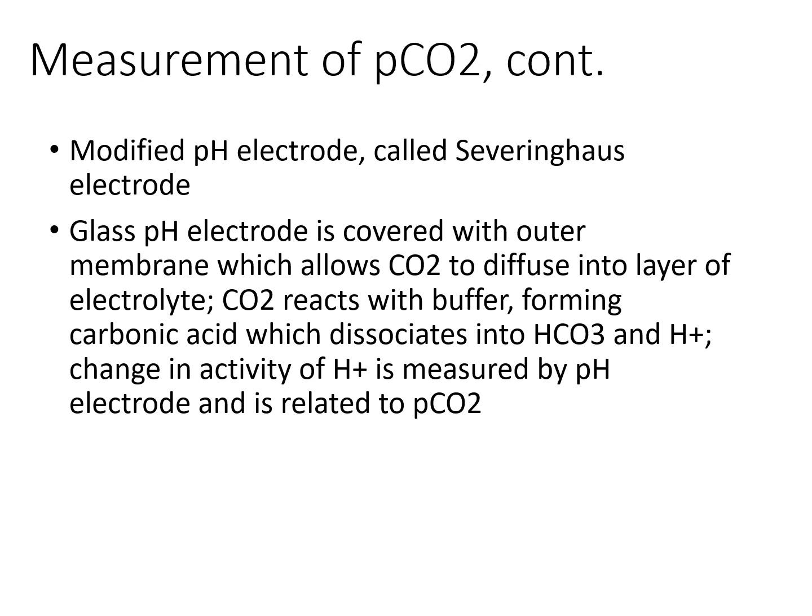This reaction increases the concentration of hydrogen ions in the electrolyte. The pH electrode then measures the change in hydrogen ion activity, or the pH, within the electrolyte solution. Since the increase in hydrogen ion concentration is directly related to the amount of CO2 diffused, the change in pH is proportional to the PCO2 of the sample. This allows indirect but precise measurement of carbon dioxide pressure.